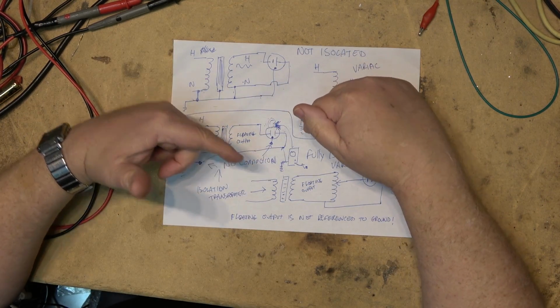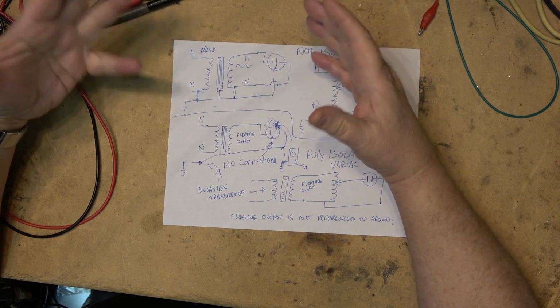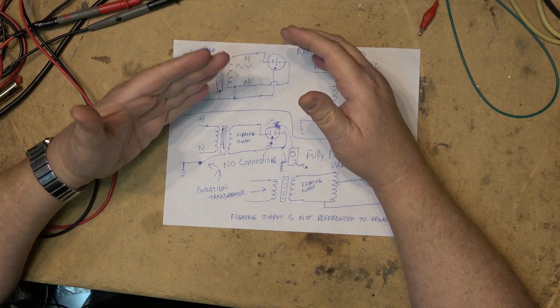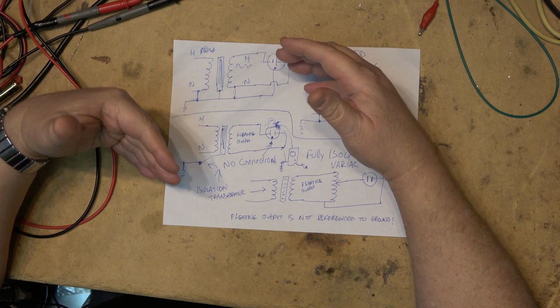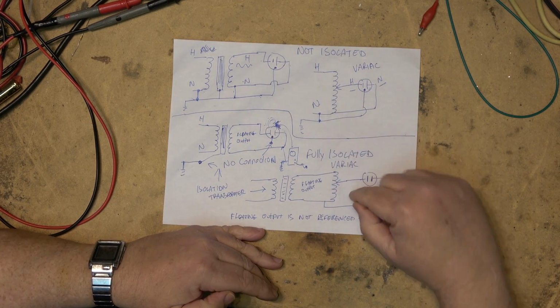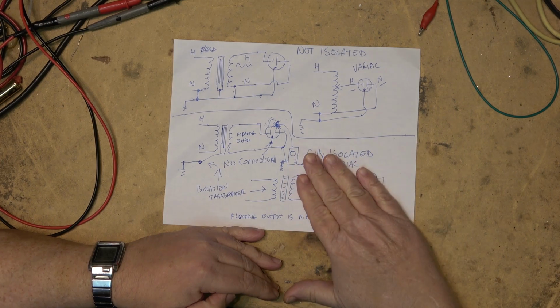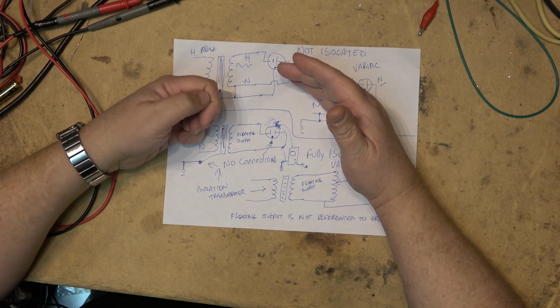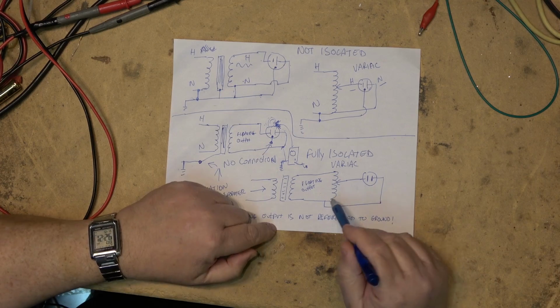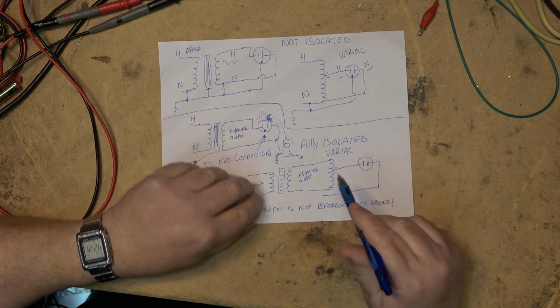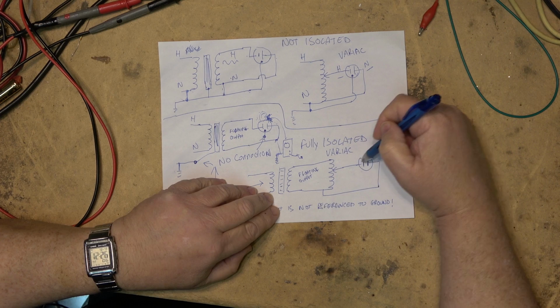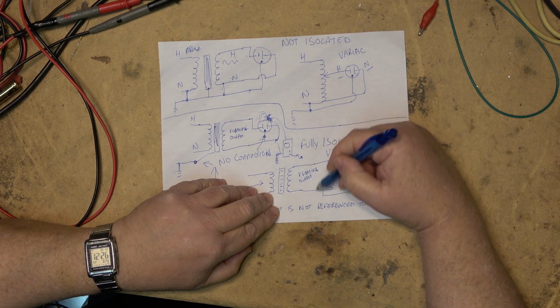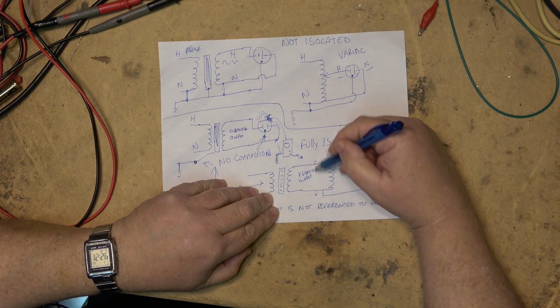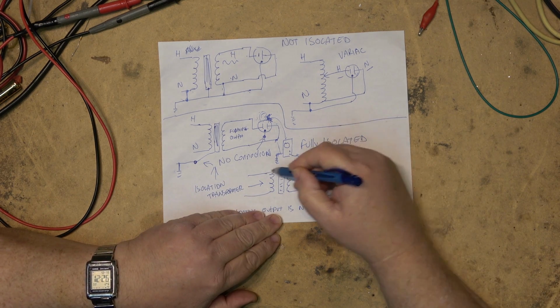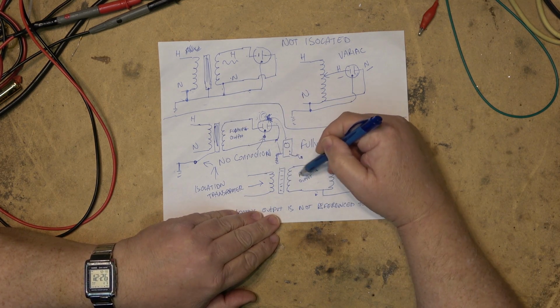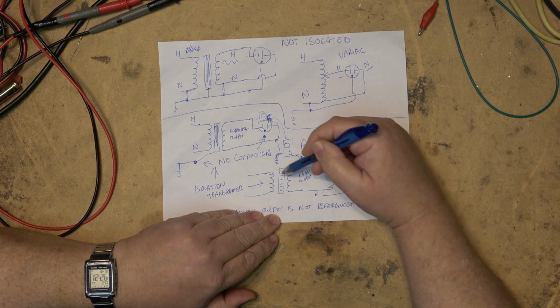Now, you could still get a shock through an isolation transformer. The idea behind an isolation transformer is it prevents you from becoming the path to ground. So with either of these floating, and there's no connection between the earth ground and the equipment, if you are touching something that's ground, you are not going to complete a circuit from line. You will basically do what I did with that resistor. You will pull whatever side you're connected to towards ground through you, but no current will flow because there's no direct reference back here. It's not connected back to the utility pole. It's connected only to the output of your transformer.